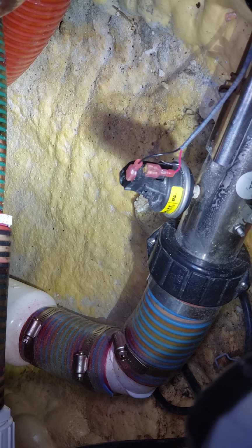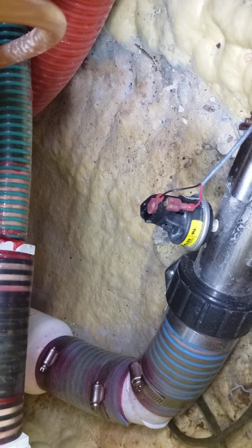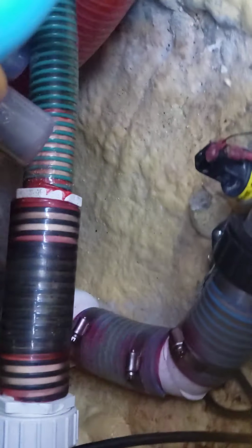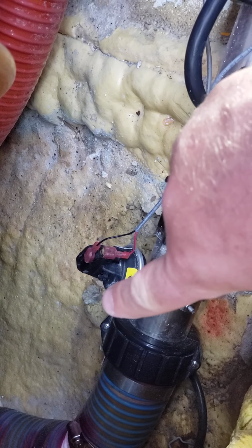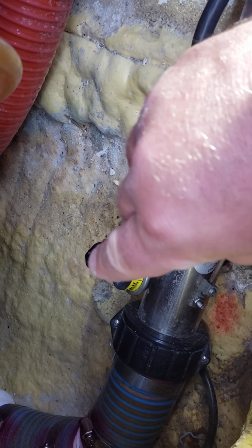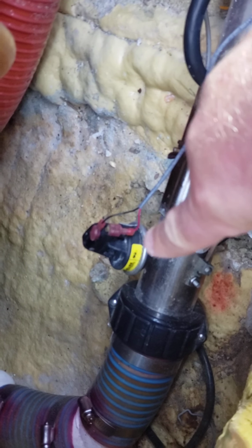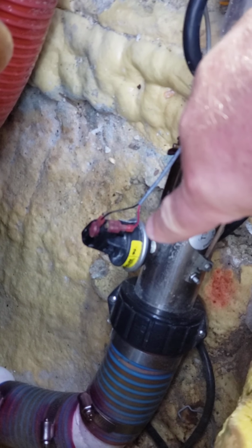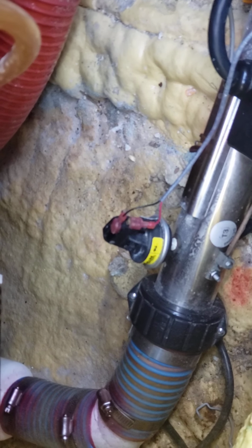Now, what makes sense is to back that little adjuster knob out. Okay, I don't know if I can reach and run the camera at the same time here, but we'll give it a shot. Okay, so, no, I can't. So, that little adjuster knob right there, I'm going to back that out a few turns to move that spring up this way, which will take away the spring pressure that's pushing on that diaphragm. That diaphragm will be right in this area here, okay? And we'll do that. We'll give it a couple turns, and we'll just see if that code comes back on. If it does, I'll do it some more and back it out.